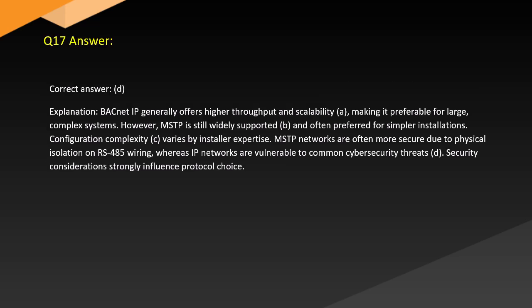Answer. Correct answer: D. Explanation. BACnet IP generally offers higher throughput and scalability, making it preferable for large, complex systems. However, MS/TP, B, is still widely supported and often preferred for simpler installations. Configuration complexity, C, varies by installer expertise. MS/TP networks are often more secure due to physical isolation on RS-485 wiring, whereas IP networks are vulnerable to common cybersecurity threats, D. Security considerations strongly influence protocol choice.